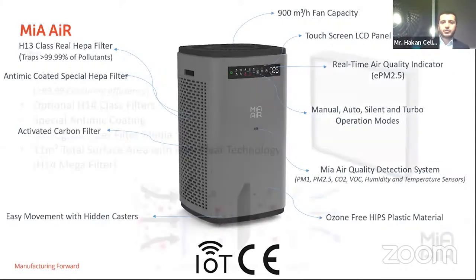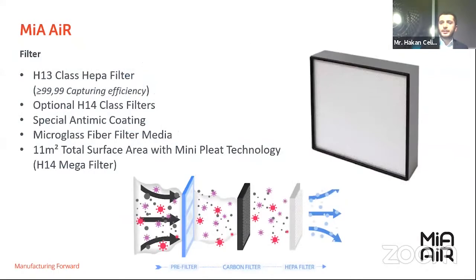Let's go deeper into the equipment. The filters which we are using on the MIA Air Purifier are EN1822 certified filters. They are coated with an anti-mic, antimicrobial solution. This filter is completely the same as what we provide to precise industries like pharmaceutical production, semiconductors, hospitals, even surgery rooms. The filters are fully the same. Total filter media area is around 8 square meters for each unit. This is one of the highest in the market.